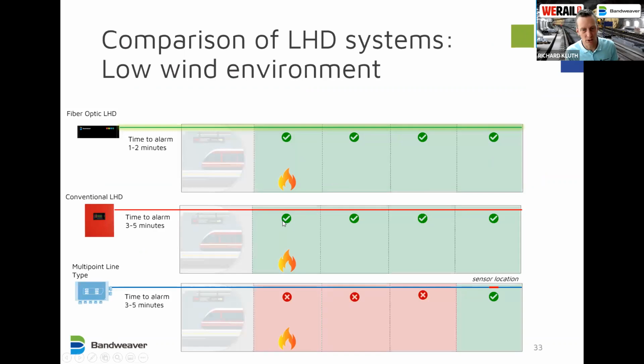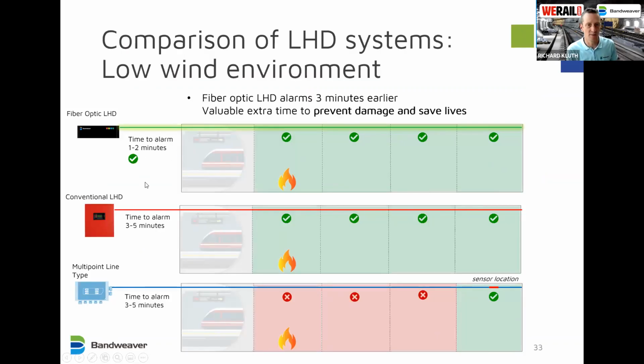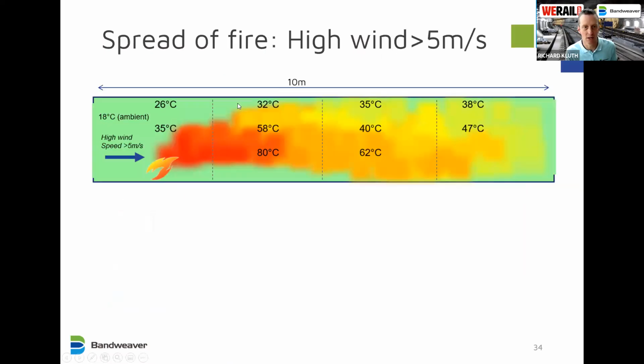The conventional linear heat detection triggers in all zones. That's predominantly because they've got full coverage. The multi-point triggers, but it triggers only in the zone where it has the sensor within the time frame. And the time frame is that the fiber optic linear heat detection triggers in 1 to 2 minutes. The other systems, 3 to 5 minutes. So this buys you 3 minutes extra time, which is valuable extra time to prevent damage and save lives.